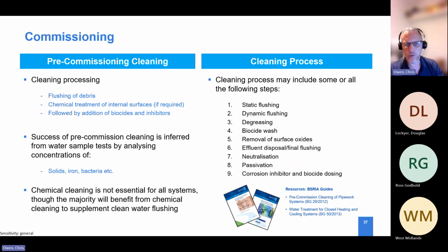However, thin wall tubes are actually supplied with an internal protective coating, and the problem is that the chemical treatment taking place to clean the tubes was actually stripping off that coating. So again, leaving the exposed virgin metalwork open to the elements, and that was again initiating corrosion. So again, making sure that if you are flushing and leaving systems, that biocides and inhibitors are used.